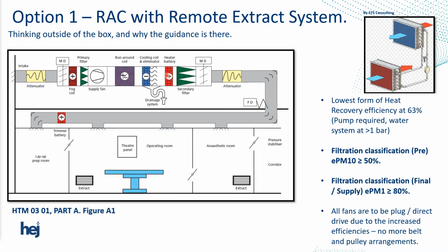The heater battery is the final major component, and then we have the filters that sit at the end, which would be to that classification that I showed you on the previous slide. Fire dampers take us through the floor. We have the operating theatre, and then you can see we give a trimmer battery to the lay-up prep room to offset that. And there's design stuff that you can do with that as well if it's a UCV operating theatre. Filter classifications are a minimum standard over here. We have ePM10 50% for the pre, which is this one, and ePM1 greater than or equal to 80% on the final filter, which is this one.